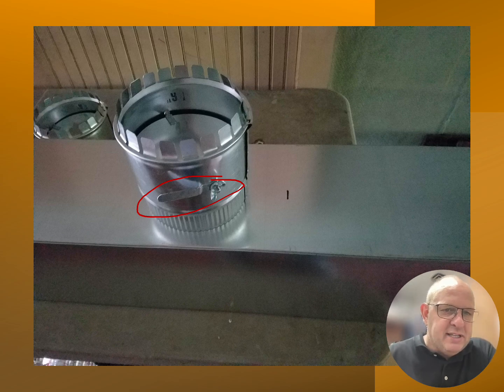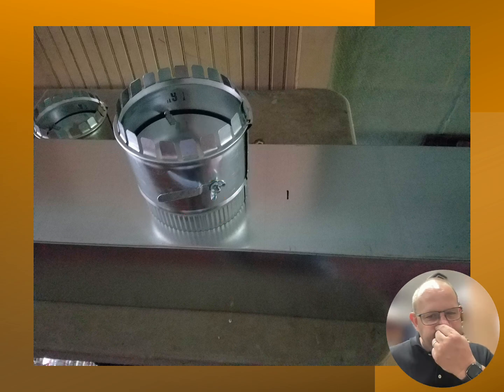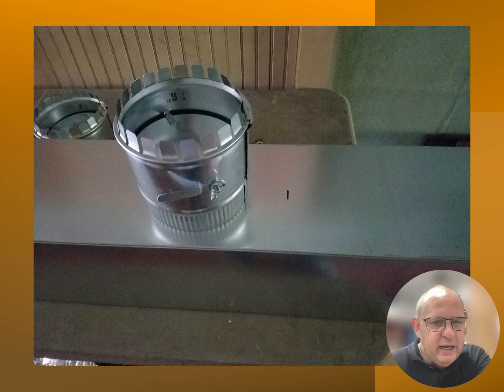Now that damper is going to sit on the inside of the takeoff itself, and you can see that metal right there. This lever on the outside of the takeoff is what we're going to use to move that damper on the inside to adjust the airflow coming out of our branch ducts so that we can make sure to give the proper CFM value to that room in order to cool and in order to heat that room up.